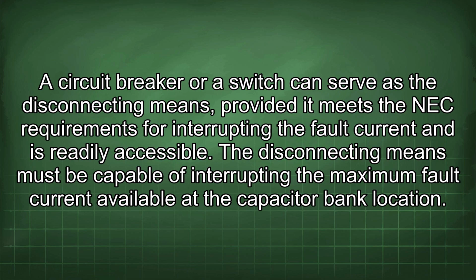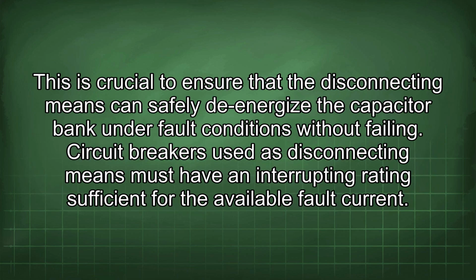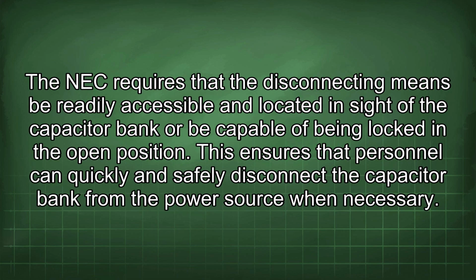The disconnecting means must be capable of interrupting the maximum fault current available at the capacitor bank location. This is crucial to ensure that the disconnecting means can safely de-energize the capacitor bank under fault conditions without failing. Circuit breakers used as disconnecting means must have an interrupting rating sufficient for the available fault current. The NEC requires that the disconnecting means be readily accessible and located in sight of the capacitor bank or be capable of being locked in the open position. This ensures that personnel can quickly and safely disconnect the capacitor bank from the power source when necessary.